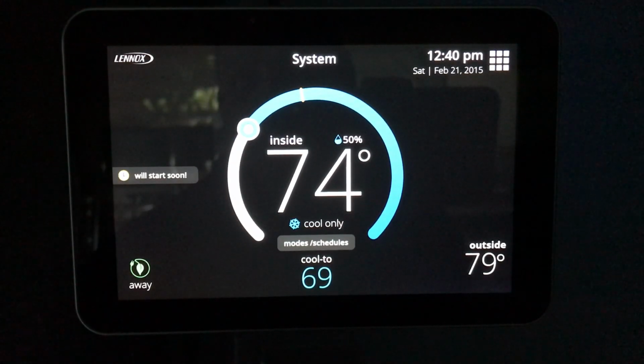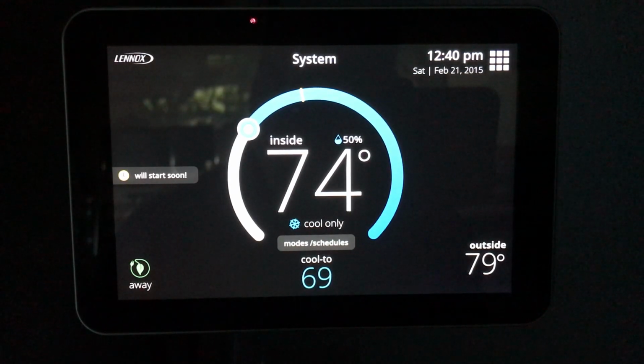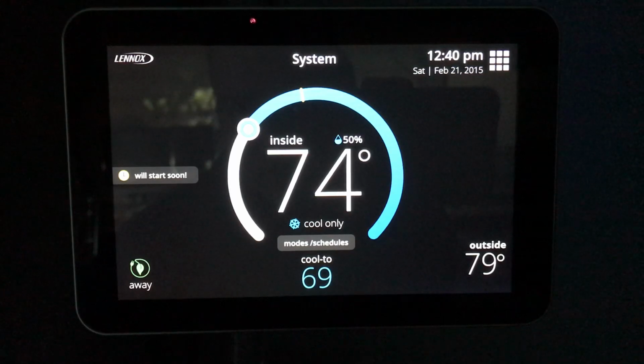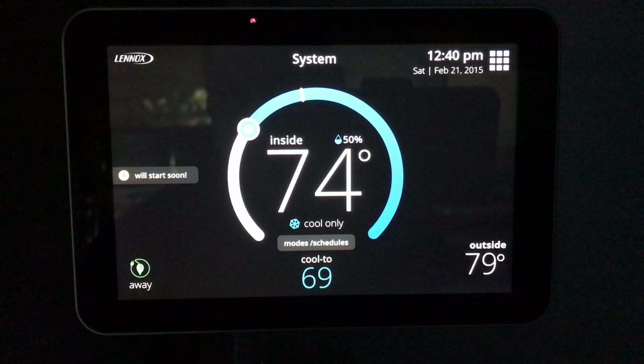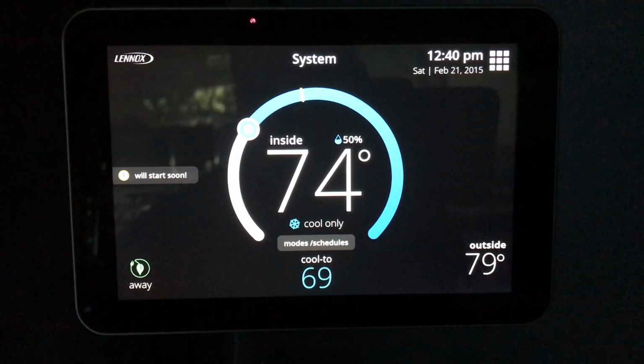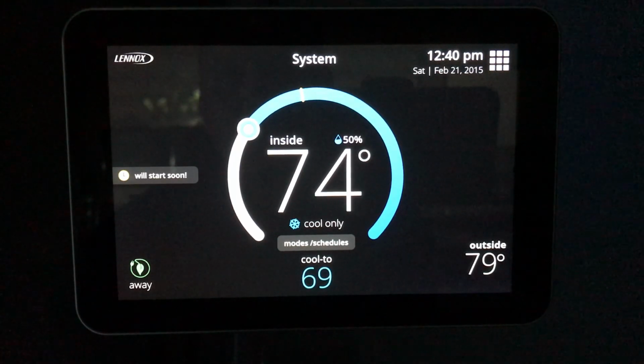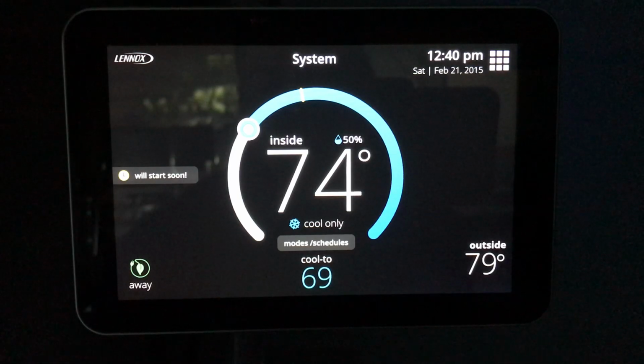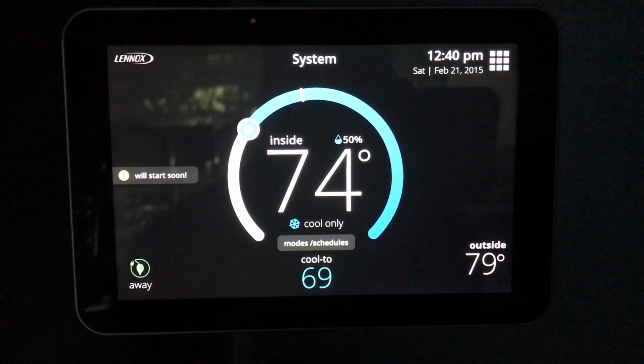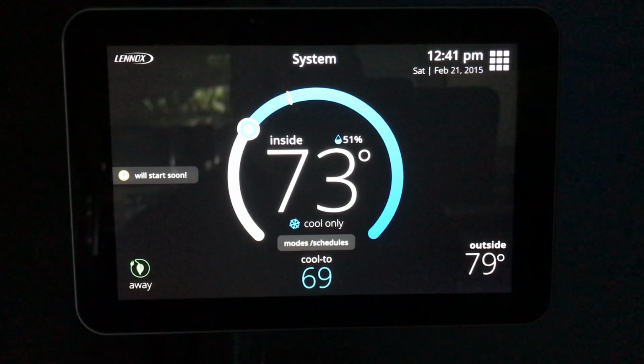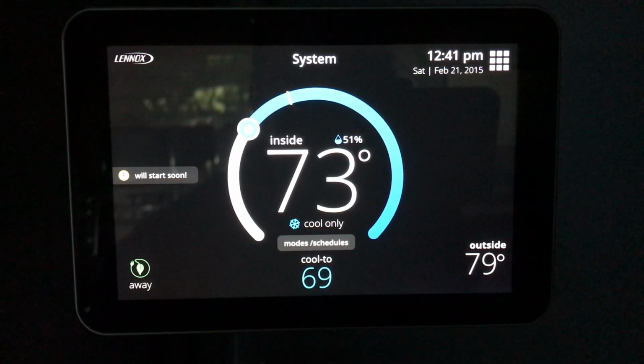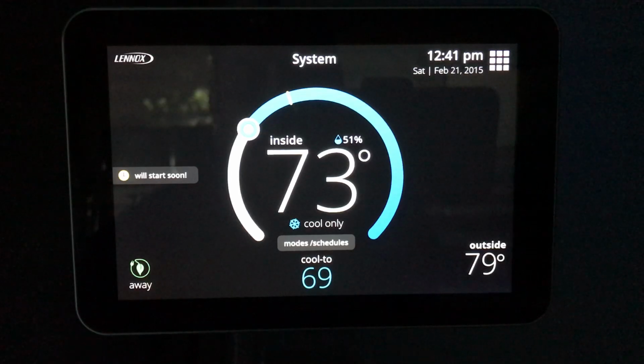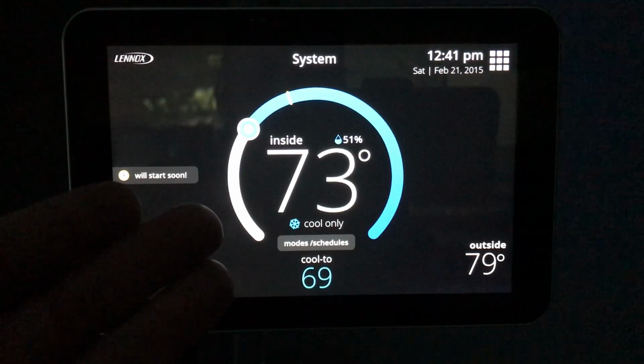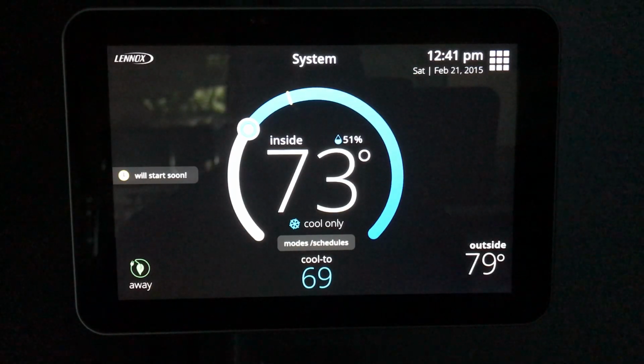And as long as we know this system is always running, especially on the air conditioning side, it will always continue to dehumidify. So let's just focus on set point, because most often folks say, let's set it to 72, and they're not focused necessarily on trying to set a comfortable level of humidification. So again, when the dehumidification is on, that's when we have a lot of folks describing that the system is running all the time and it virtually never achieves the set point, because they are correct. The thermostat is ignoring the set point and focusing on that dehumidification. And right now, this is where I was saying give it just a few minutes and you can see that the temperature will start to adjust based on your calibration. Hope this helps, guys.